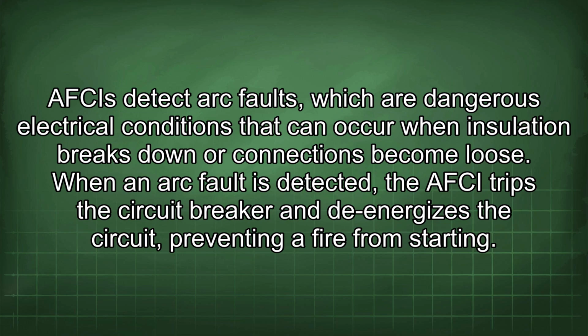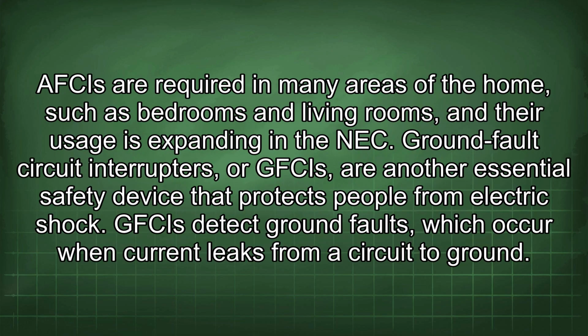When an arc fault is detected, the AFCI trips the circuit breaker and de-energizes the circuit, preventing a fire from starting. AFCIs are required in many areas of the home, such as bedrooms and living rooms, and their usage is expanding in the NEC.